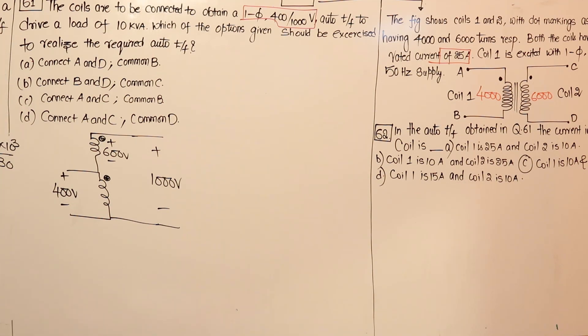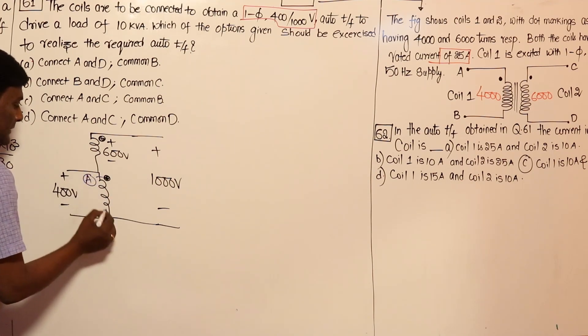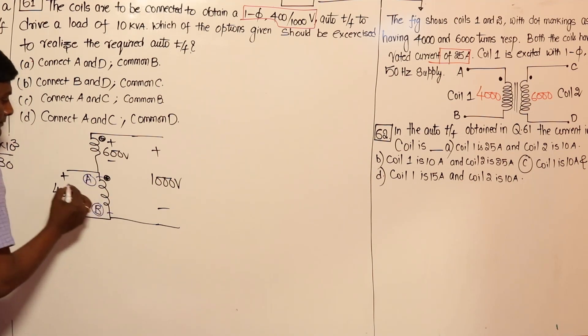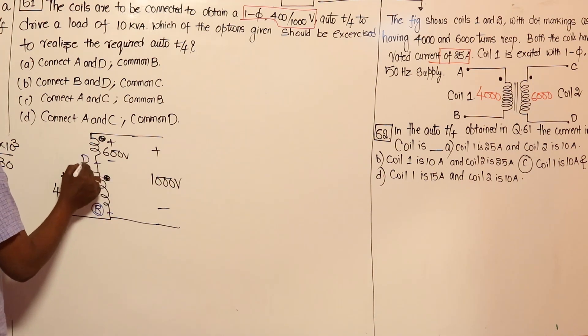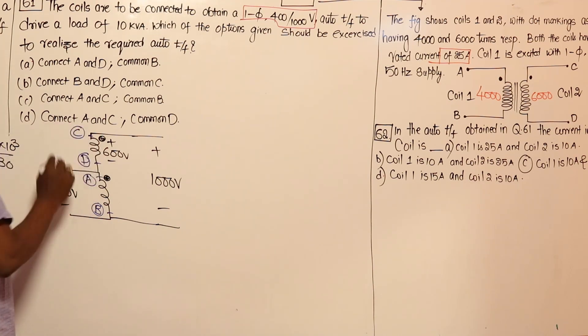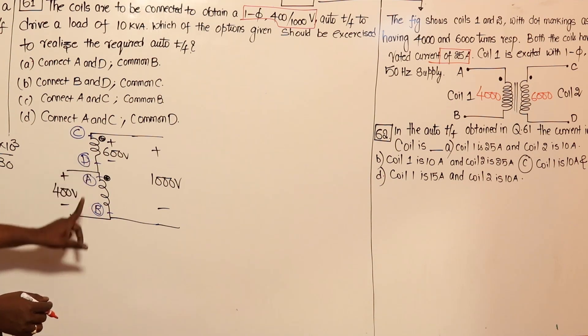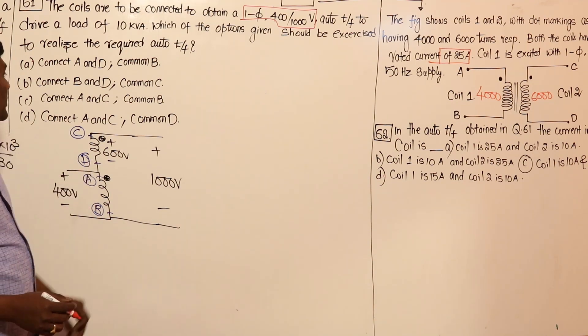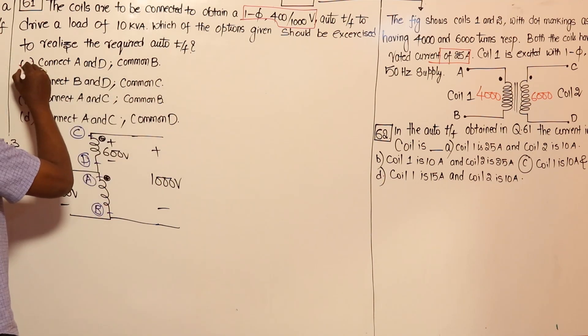For the connection diagram: terminal a and b are given for coil 1 (the 400V side), and for the second coil, the undotted terminal is d and the dotted terminal is c. To form the additive auto transformer connection, we connect terminals a and d together, and b is the common terminal.